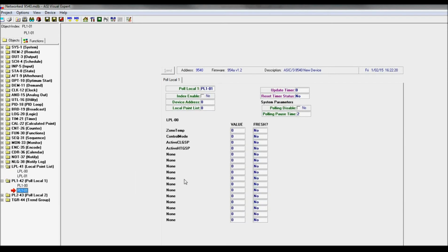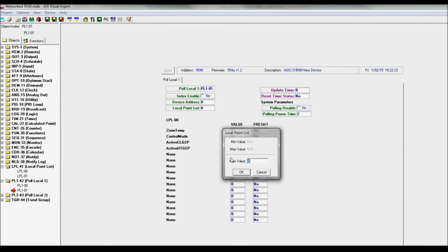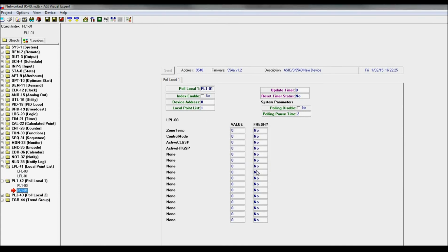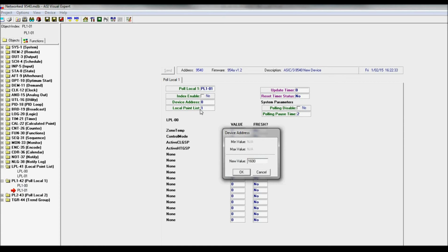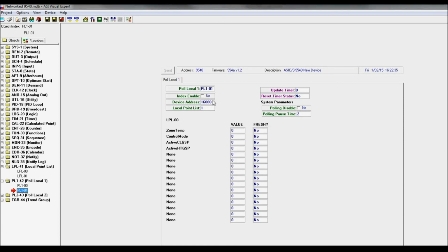So I'm going to come down here, and because this is set at a 0, it's going to look originally at whatever was at instance 0's list. We're going to go ahead and put our controller address in, 16000. We're going to enable it. And I'm going to go ahead and come up to this instance and refresh this instance. And now you see that once again, we have information and we have our set points, and it's pulling different data.